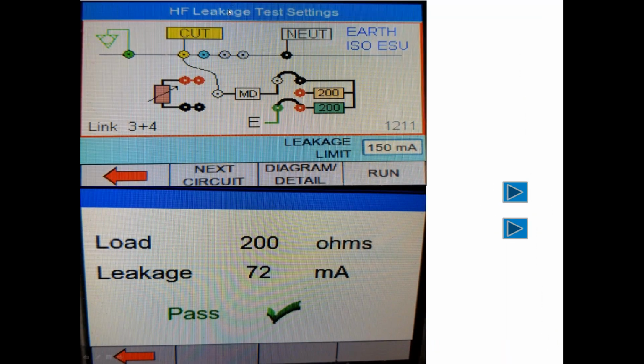So again, there is our test circuit, and the bottom photograph shows what the test screens could look like. See that we provide the resistance value, 200 ohms, and the leakage current that we measured. And above on the test screen is where we can set our leakage limit. Again, the default would be 150 milliamps, but if the manufacturer specified something different for bipolar, 69 milliamps for instance, that could be set in the block where it says leakage limit. And again, in an auto test sequence that we provide you free of charge, that would be preset for you for that particular generator type.